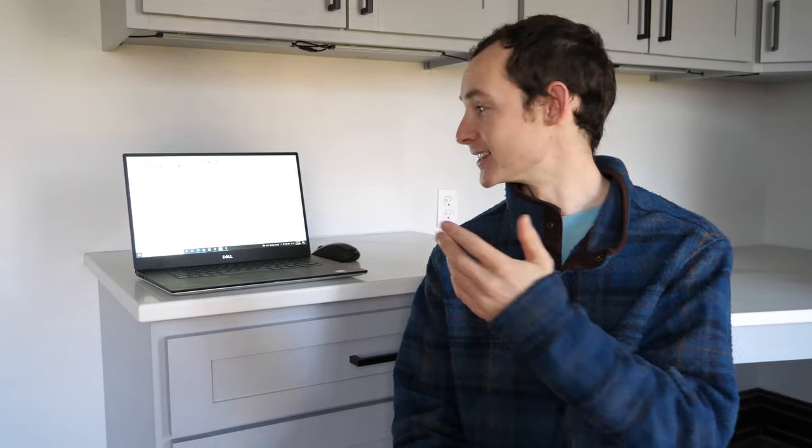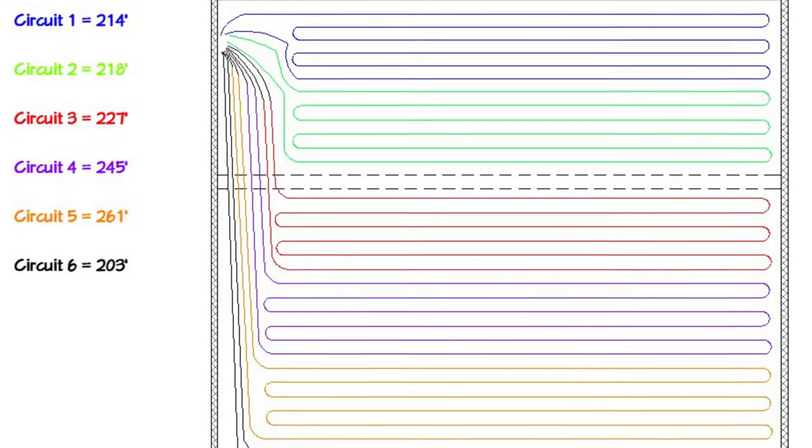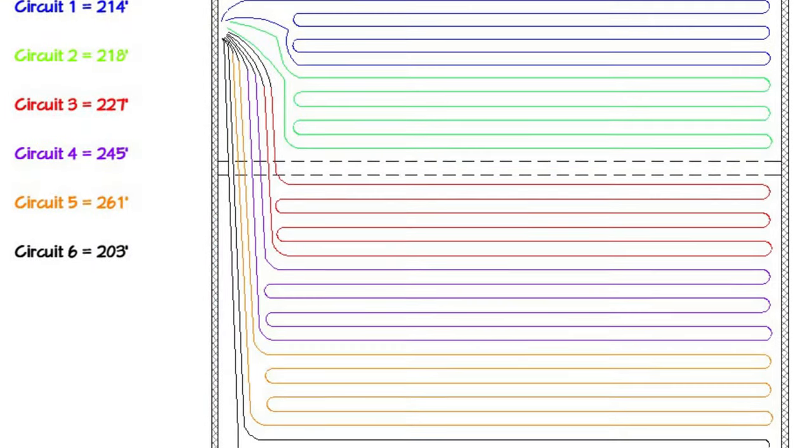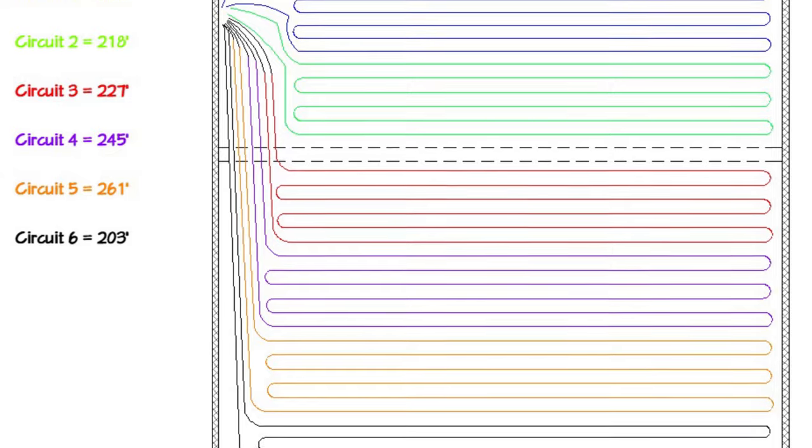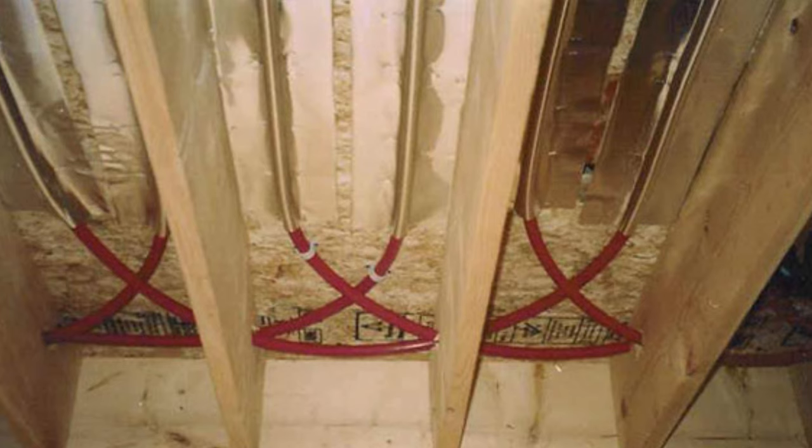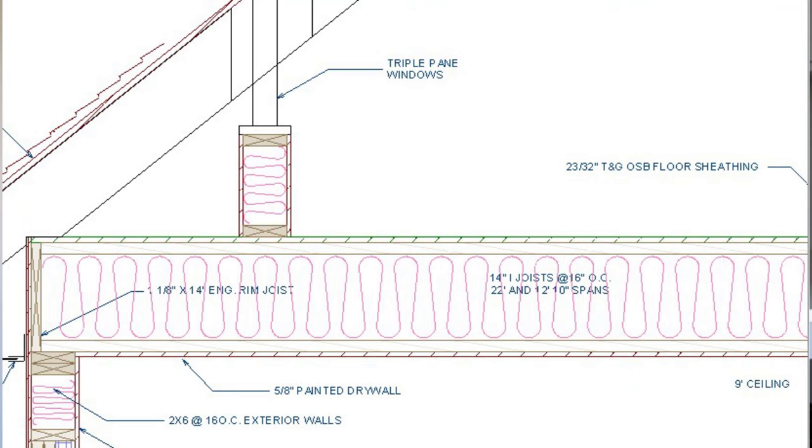For my garage, this is about 1,240 square feet. I did a preliminary layout in the CAD software and that put me right around six circuits. We're going to be doing a system upstairs too on the whole upstairs floor, and that's going to probably be another five or six circuits run in between the joist bays and stapled up to the bottom of the subfloor. We'll insulate below that with some batt blanket, probably R-23 rock wool or something like that.